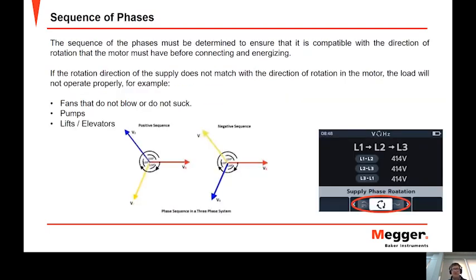So the sequence of the phases must be determined to ensure that the motor rotation direction will be correct based on the connection of the winding. This will ensure that the load operates correctly. So, for example, the fan will blow when it should, or suck, depending on what the function is. Applies to pumps and lifts or elevators.